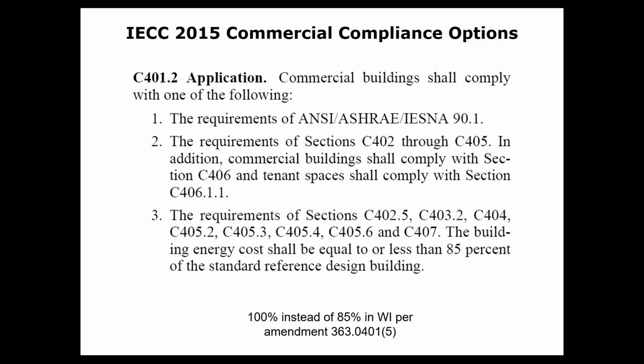You always still have to do the mandatory provisions, whether you're in section number 2 or 3 on this page here. You still have to do the mandatory stuff. It's the prescriptive stuff that you could trade off. So maybe you can't do the VRF job with economizers because economizers don't work well in that application. So all that energy you would have saved with the economizer, you're going to end up having to make up with better efficiency on the heating and cooling plant or better windows or whatever it is.